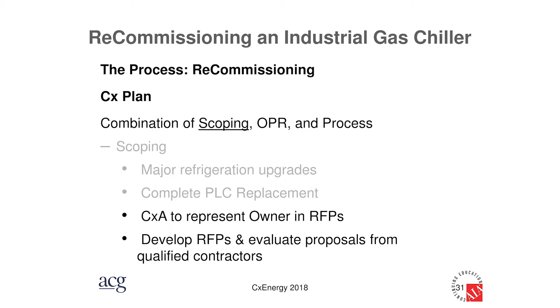The OPR started out with me asking a whole bunch of annoying questions, and they said, well, don't you know this already? I said, well, I could guess, but I wouldn't be answering it the way you would answer it. So the first thing we had to find was, what's the real set point? The equipment was designed to make the gas 40 below zero, so that was the design point. But is 40 like it never gets warmer than that, or is that the point where the equipment can start unloading? The operators did a few practice runs at different temperatures and decided they could run it between 35 and 40 below. That was really helpful, because a machine made to run to 40 has a hard time getting all the way to 45 below, but it's pretty easy for it to get to 35 below and then modulate between 35 and 40.